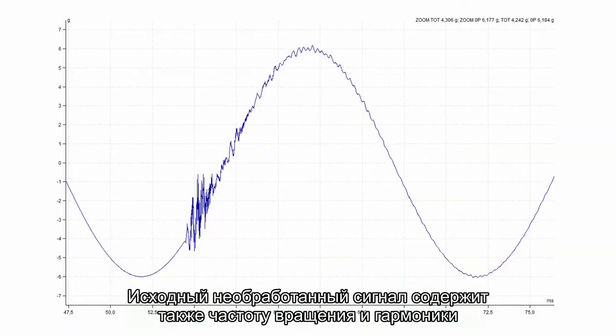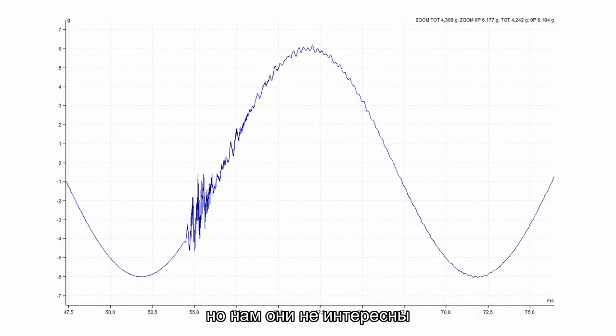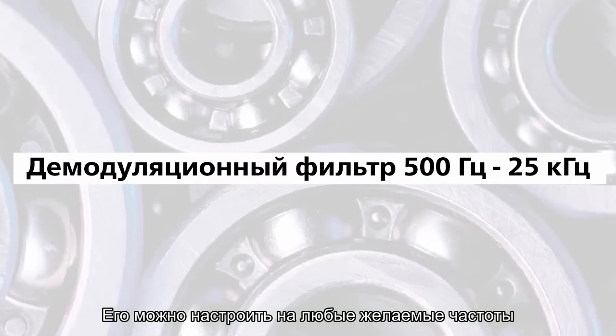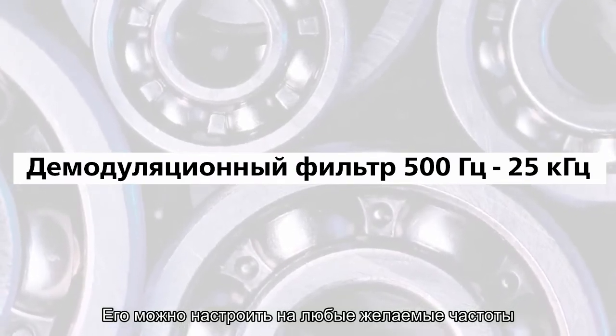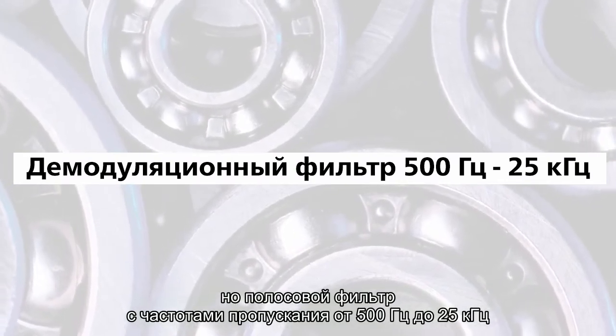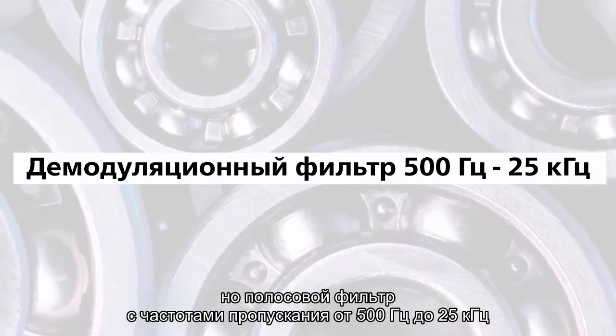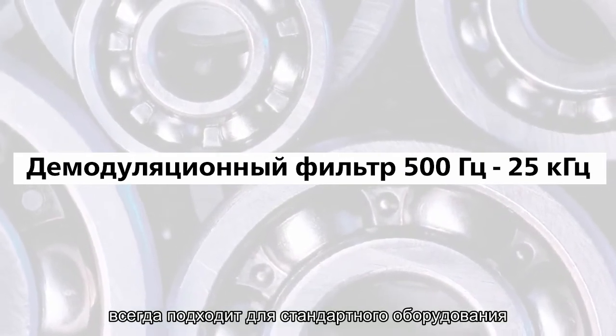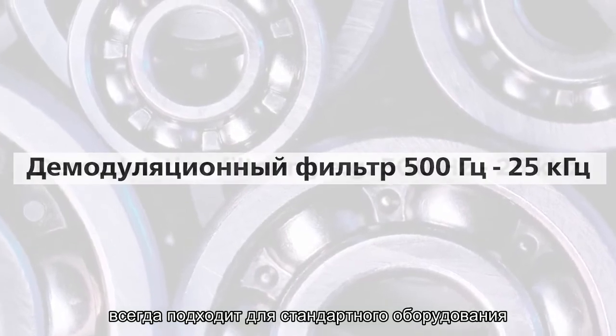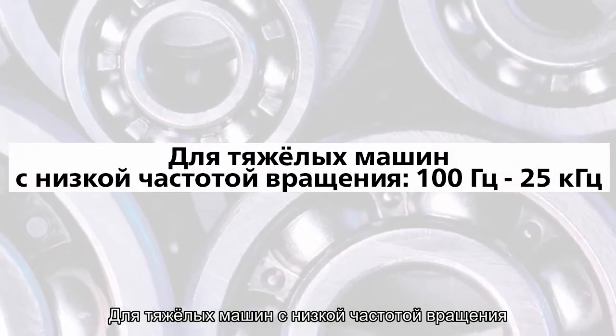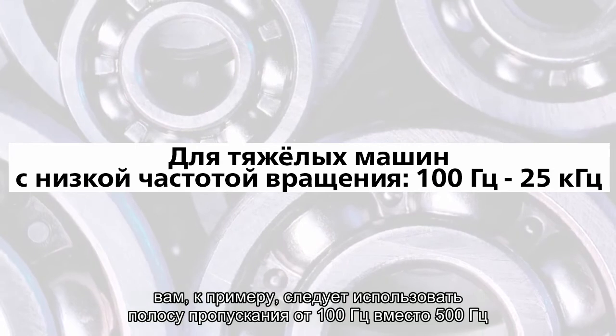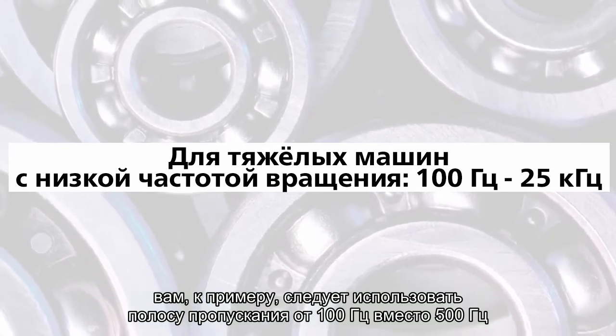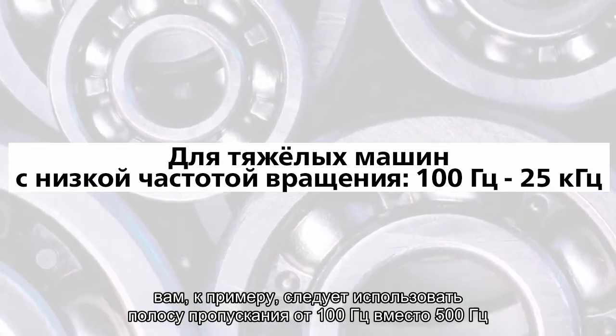The initial raw signal contains also the speed frequency and the harmonics. We are not interested in them. That is why we firstly use the demodulation filtering. You can set it to any specific frequencies. But the band pass from 500 hertz to 25 kilohertz always works for standard machines. For heavy low speed machines you should use for example 100 hertz instead of 500 hertz.